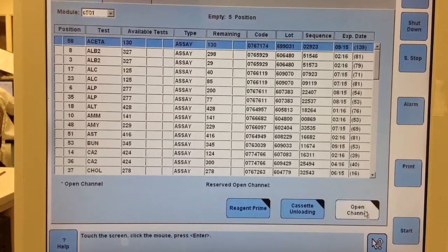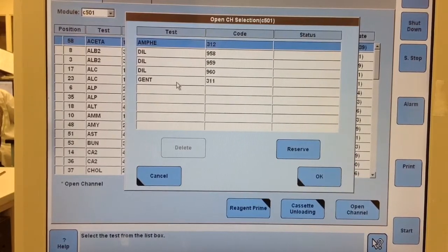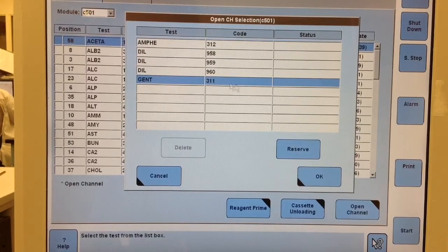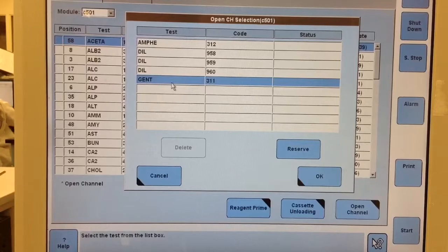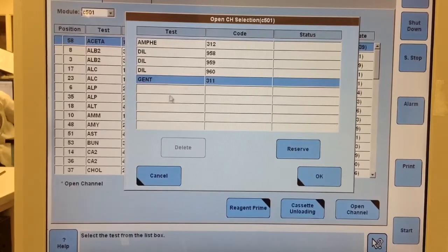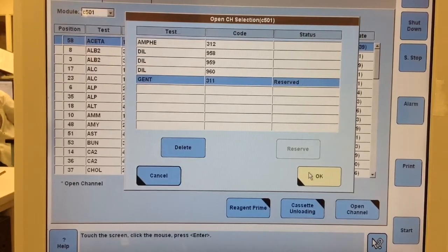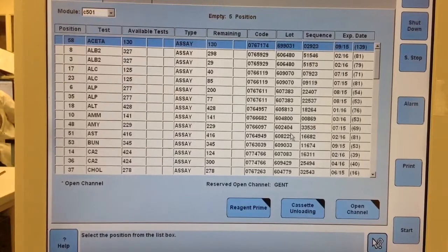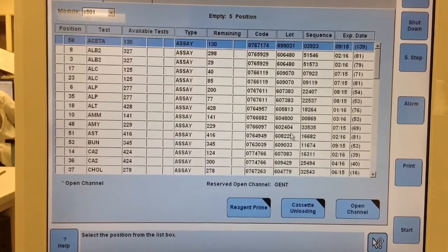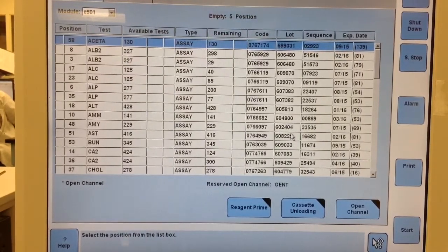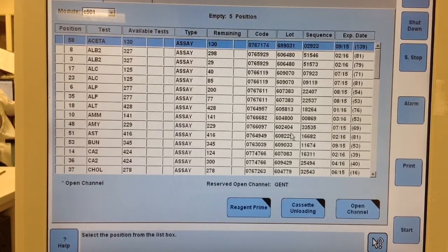After you've gotten that far, the next thing that you have to do is you click on open channel there at the bottom right, and these are the open channels you see that we have loaded. And I'm going to be loading gentamicin, so you click on gentamicin. And then after that, you want to select reserve, and then OK. And what that does is it sets up the next cassette to be loaded onto the Cobas to be gentamicin. And there you go. Thanks for watching my video.